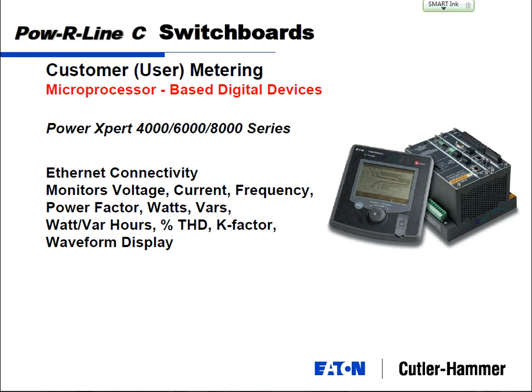I'm going to throw out an example. There's a major manufacturer in Austin, Minnesota, that built a new corporate building. When they started engineering it, they sized everything, I think, for regular lighting, not incandescent, but fluorescent or whatever that level is. They went through the design and got a nice 3,000 amp switchboard in there for their facility. They figured they'd have somewhere around 800 amps for the load. I think they had four 225 amp breakers specifically for lighting.